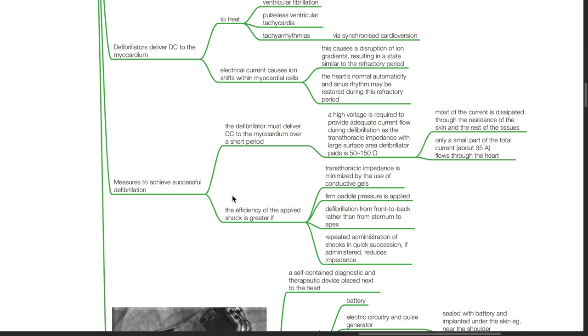Measures to achieve successful defibrillation: the defibrillator must deliver DC to the myocardium over a short period. A high voltage is required to provide adequate current flow, as transthoracic impedance with large surface area defibrillator pads is 50 to 150 ohms. Most current is dissipated through the resistance of the skin and tissues; only about 35 amps flows through the heart. Efficiency is greater if transthoracic impedance is minimized by use of conductive gels, firm paddle pressure, defibrillation from front to back rather than sternum to apex, and repeated shocks in quick succession.